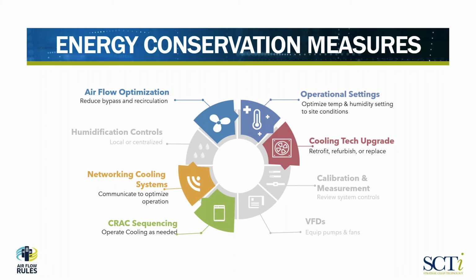In many cases, we've gone in and done work in data centers that were operating with 8 cooling units. The customer believes they have cooling problems in that data center and are looking at purchasing another CRAC unit to add more cooling. By the time we're done with our cooling optimization program, we can show that customer that site can clearly operate, and operate much better, on 5 CRAC units, or maybe even 4, which means they don't incur the additional cost for new capital equipment, and they've saved a considerable amount of money.